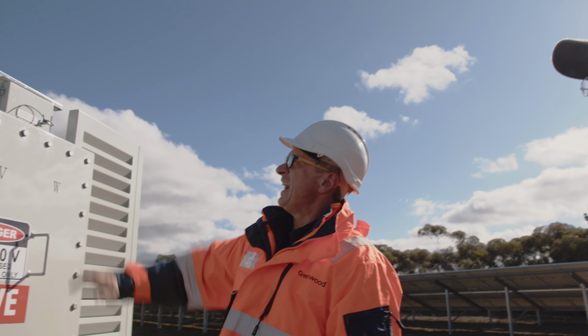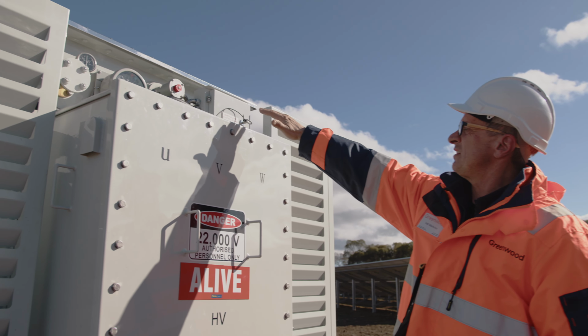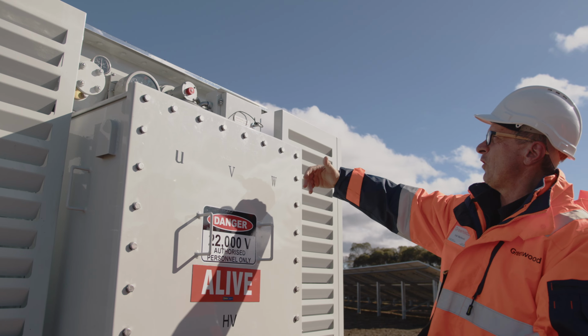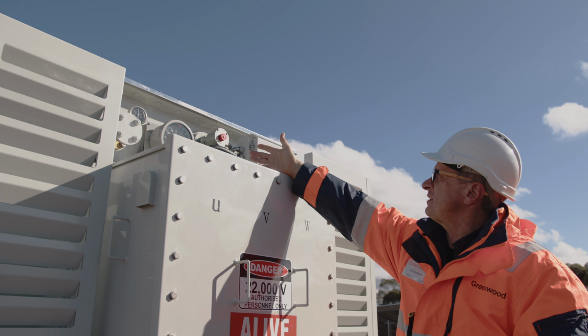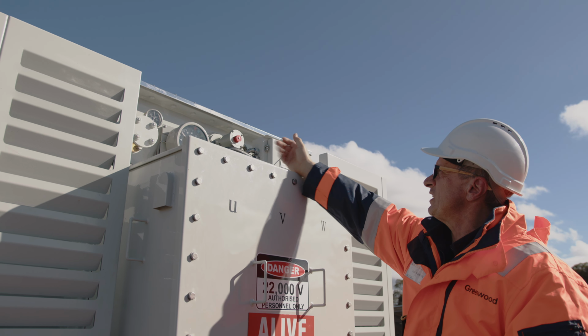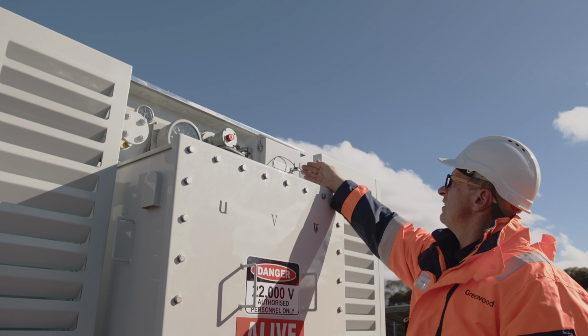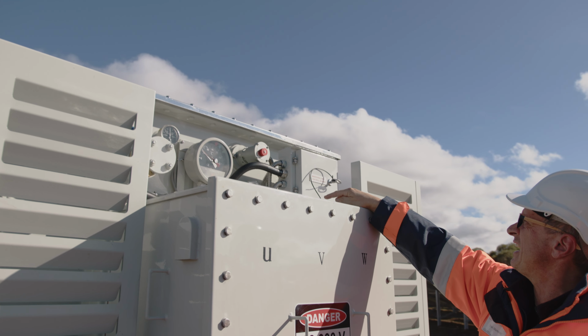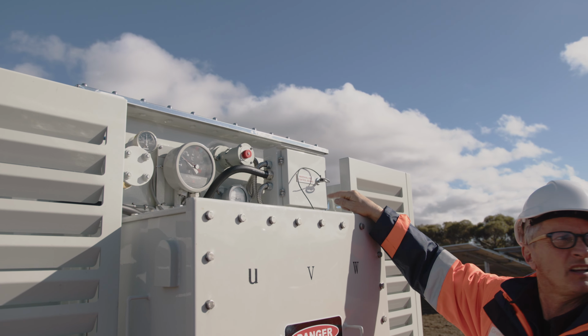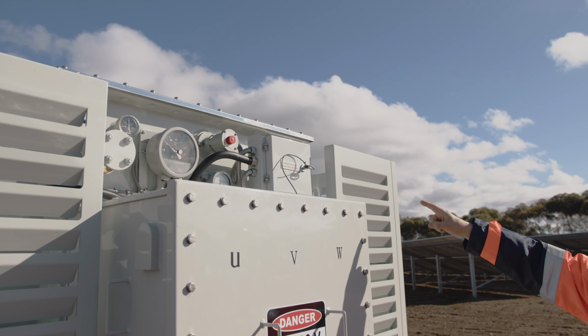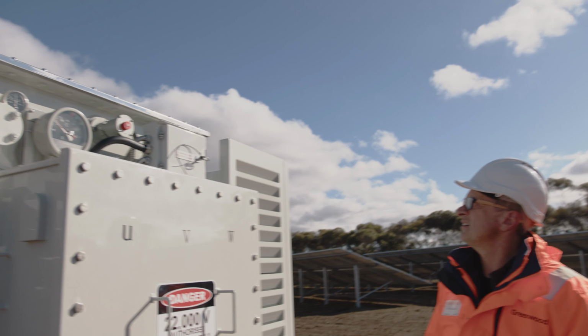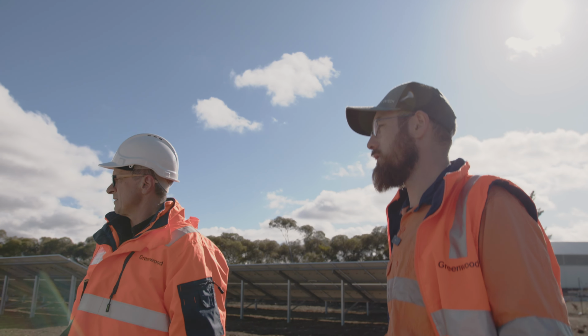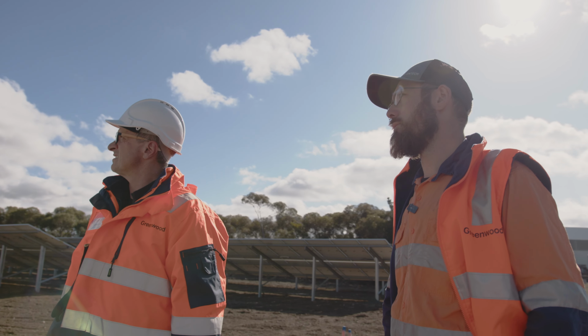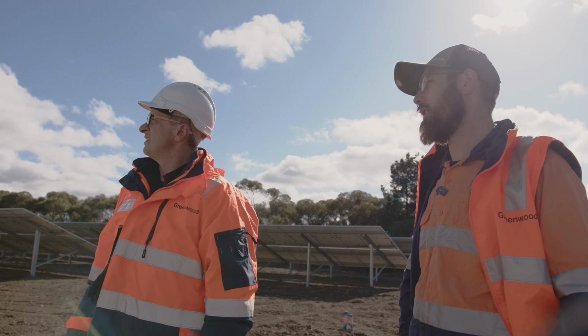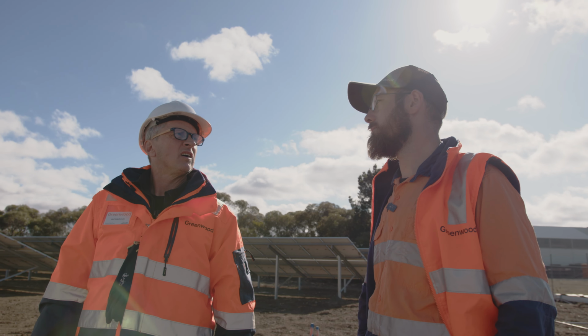Wow. And because this is an oil-based transformer, you've got an oil thermostat. So there should be oil pressure, oil temperature, and an oil level indicator. And you'll notice the marshalling box to your right there. I do. This box here is actually connected to the main HV circuit breaker for this transformer. So if there is any issue with the oil pressure or oil temperature, it'll actually turn off the HV supplying it.